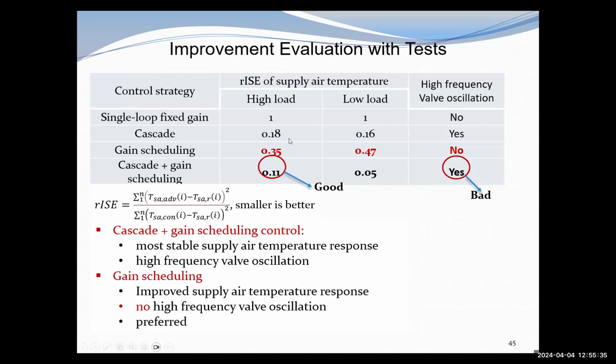And the gain scheduling control here, we can see it can also improve the supply air temperature response without the high frequency valve oscillations. Then to compromise between both, we prefer the gain scheduling control strategy. And also the gain scheduling control is easier, and it does not require the secondary controller tuning.